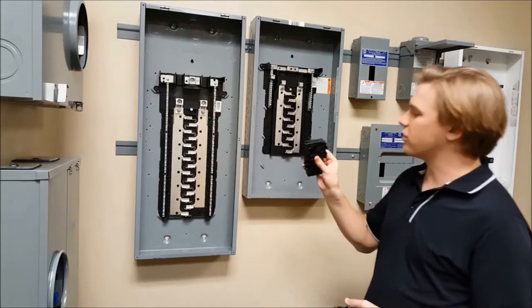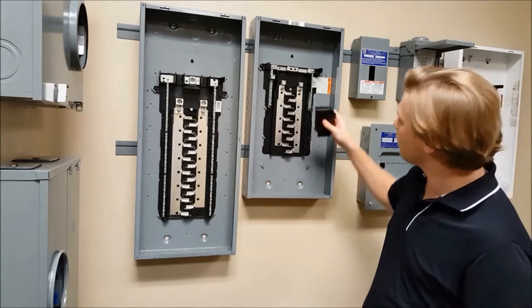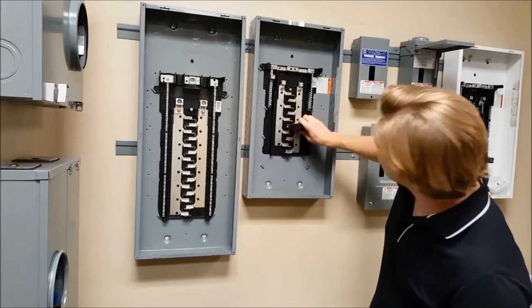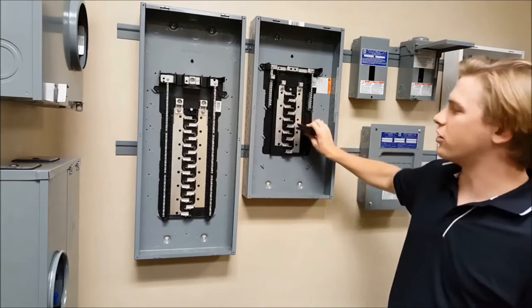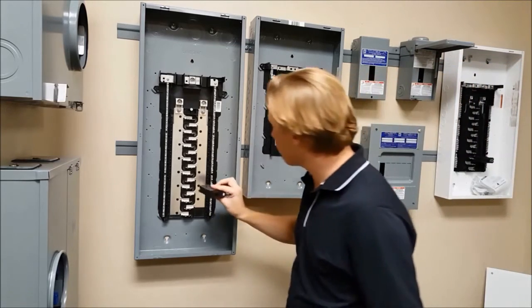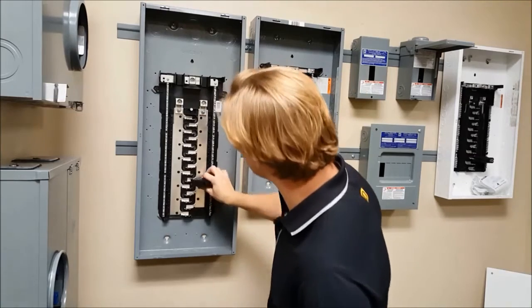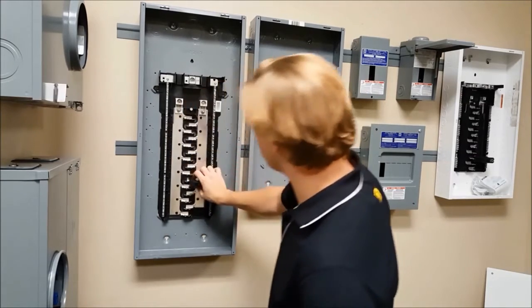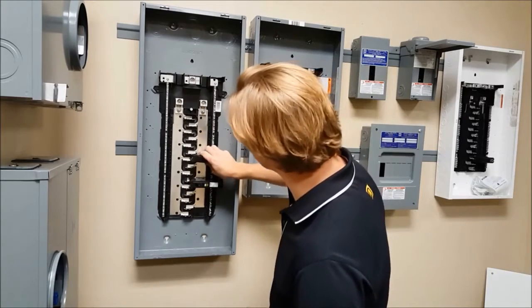You'll also see that on the plug-on neutral breaker it has a rejection feature so that it cannot be mounted in the non-plug-on neutral panel. However, on the plug-on neutral panel it will accept both the plug-on neutral breakers and the non-plug-on neutral breakers.